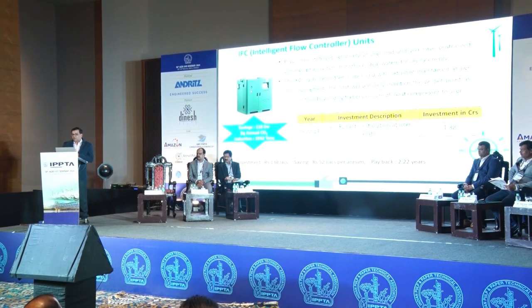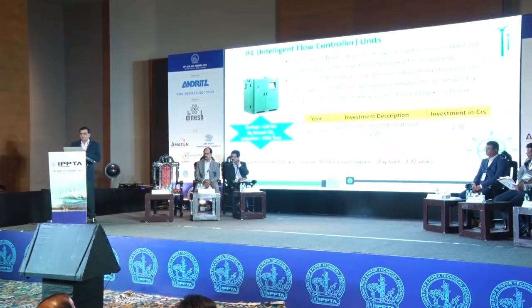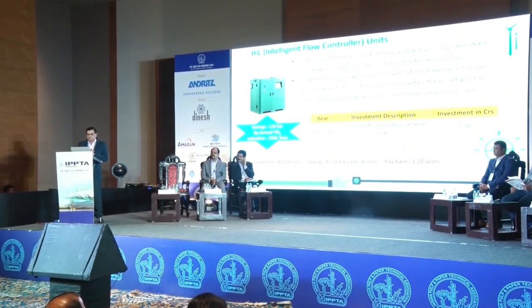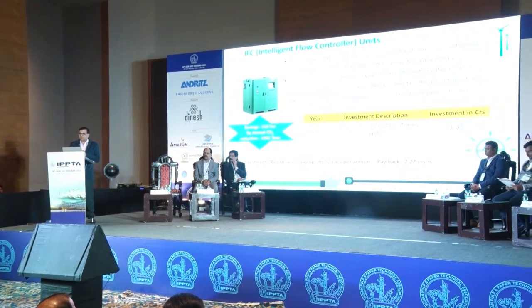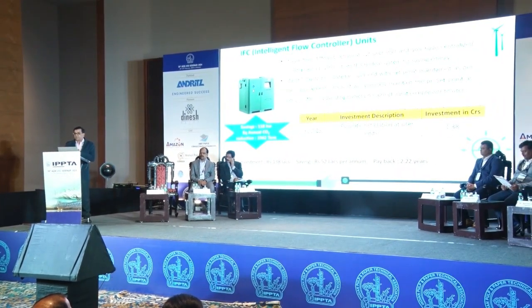Then I told you to bring all the compressors to one location, but if your users have different set points, when you centralize your compressor house you have to maintain the set point of all the compressors at the highest level, the highest consumer's demand. Then you will be supplying the higher pressure to the lower pressure set point users. So for that, the solution is an intelligent flow controller. If you install this at your user end and maintain the set point there, it will reduce the pressure and maintain only the set pressure on the downside of it.